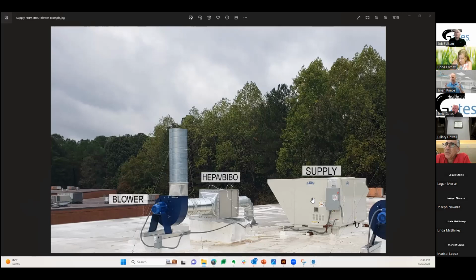We have these things in rooms called BTUs. You and I, and process and depyrogenation ovens, we put off this heat all the time. That's BTU, that's heat gain inside of a space. So you need to let the engineers know we're going to put a depyro oven in our ante room, we're going to have probably up to 4 technicians, 4 different hoods, and all this activity is happening inside the clean room and compounding spaces. And I need the target temperature to be 64F and maintain 50% RH.